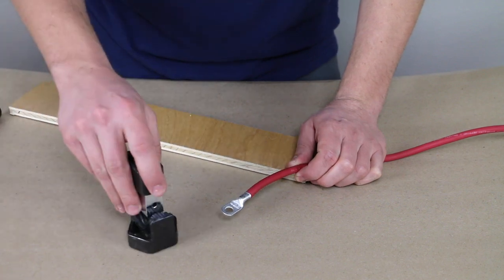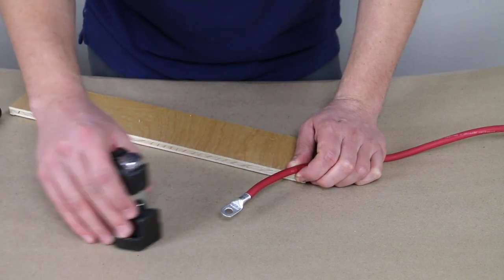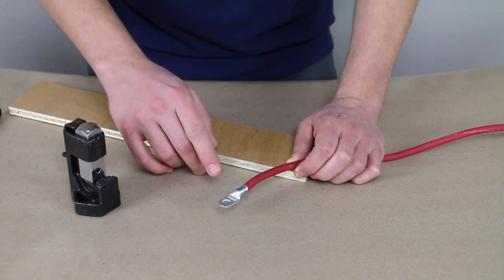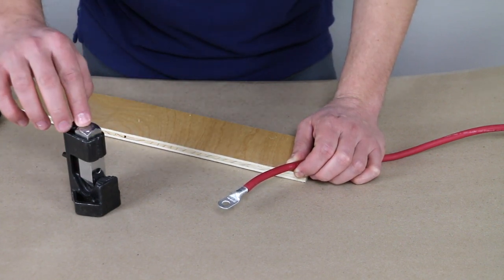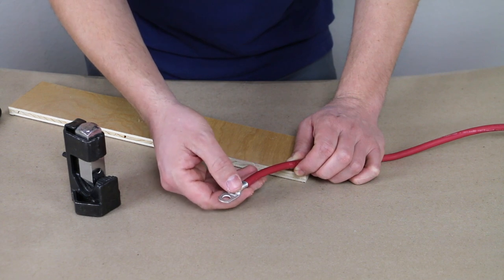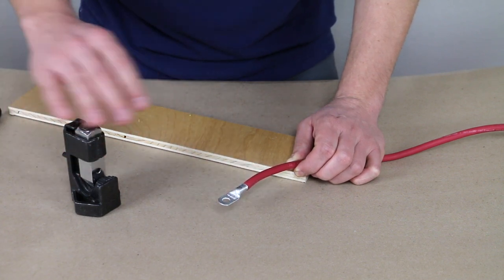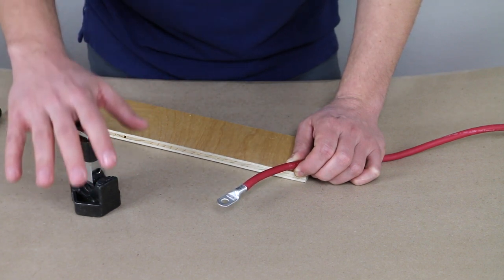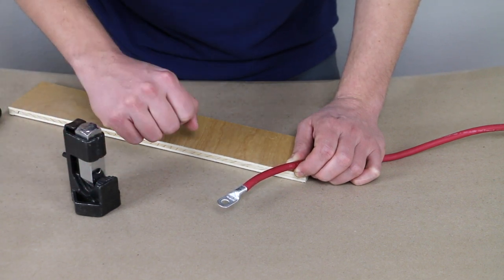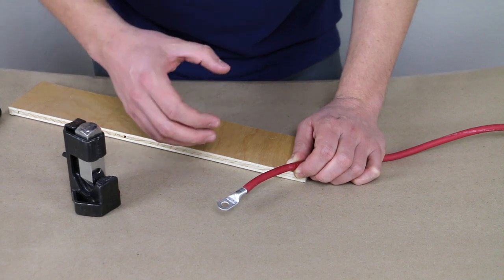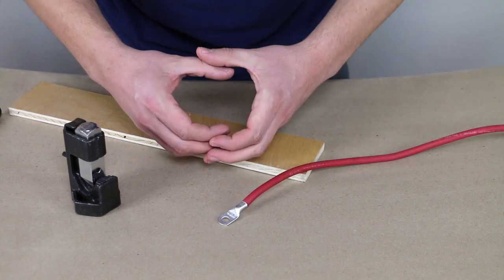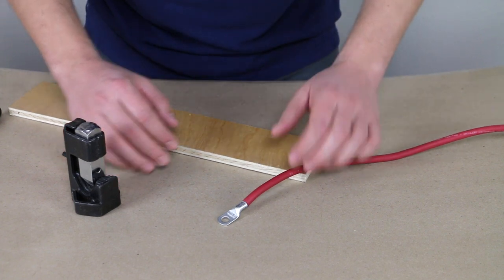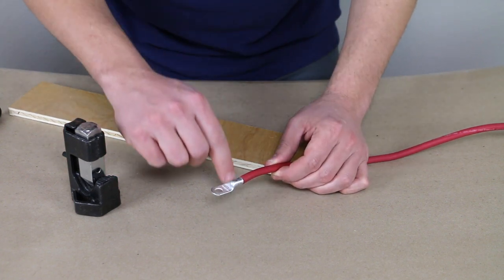Truth be told, it would be better if I did this on the concrete. But you can kind of see why I quit using this particular crimper is you kind of have one shot. You have to be a good aim with the hammer and the amount of force that you can exert with this compare even with the hammer coming down on it. And the hydraulic crimpers are just going to exert more force and they're also going to crimp all the way around the cable on six sides. They have hexagonal dies, whereas this is just going to hit it in one point.